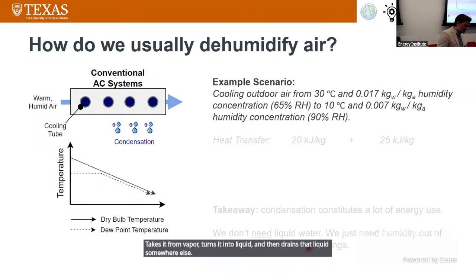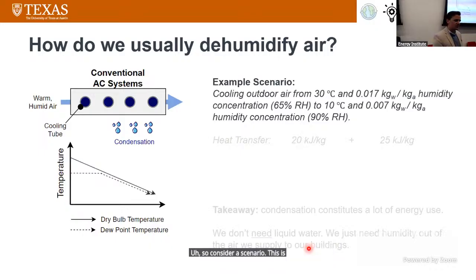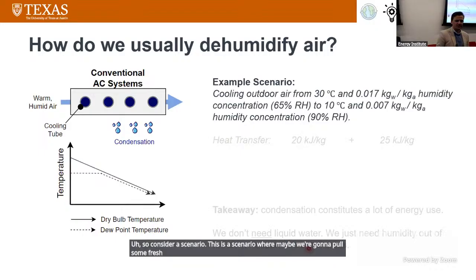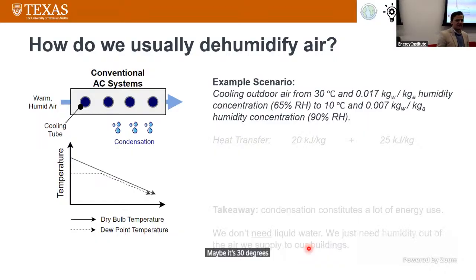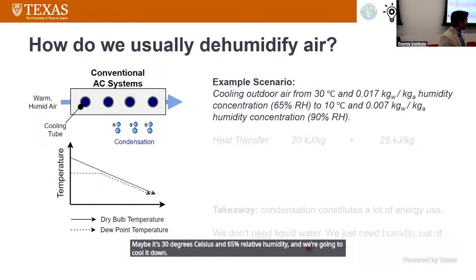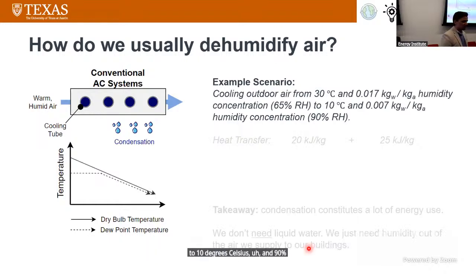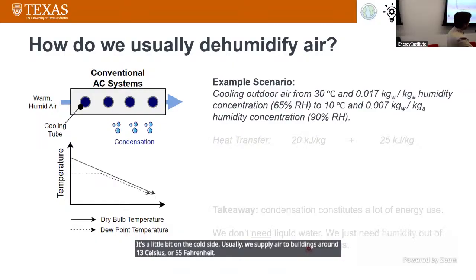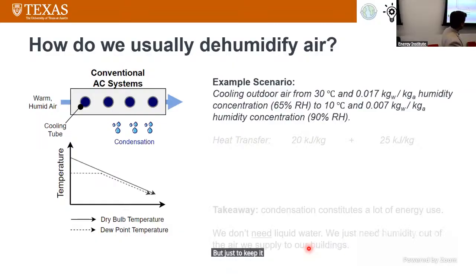Consider a scenario where we're going to cool some fresh outdoor air for a building. Maybe it's 30 degrees Celsius and 65% relative humidity, and we're going to cool it down to 10 degrees Celsius and 90% relative humidity. 10 degrees Celsius is a little on the cold side—usually we supply air to buildings around 13 Celsius or 55 Fahrenheit—but just to keep it simple, imagine we're cooling down to 10 degrees Celsius.